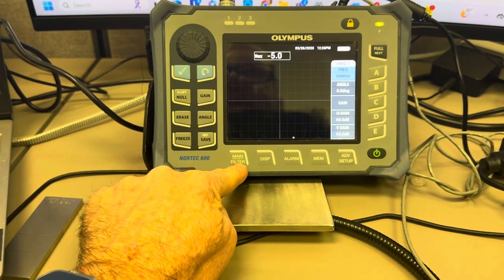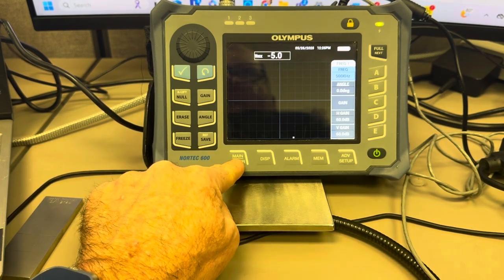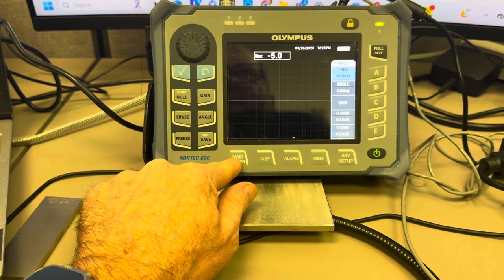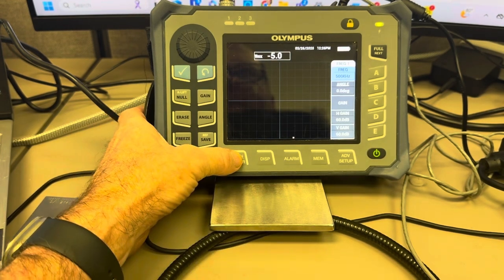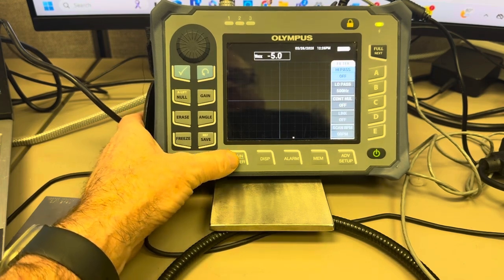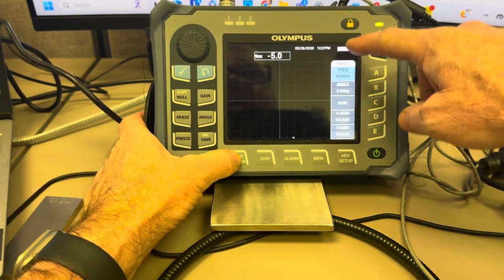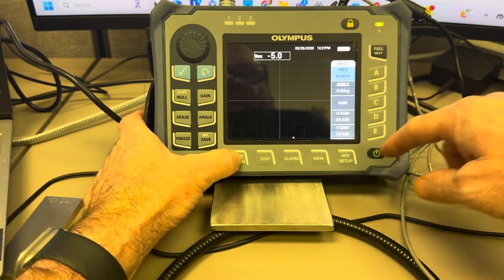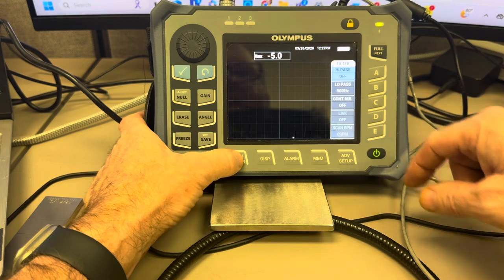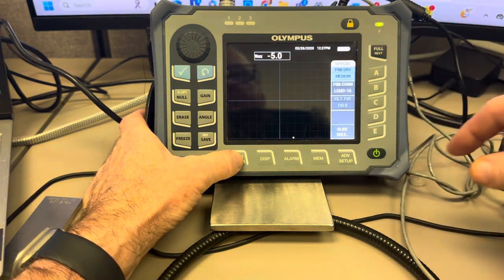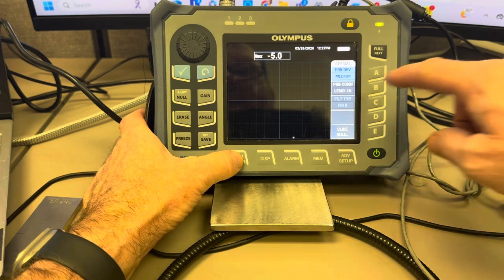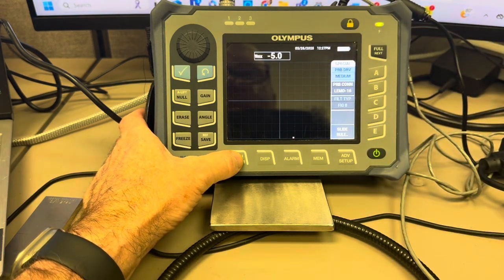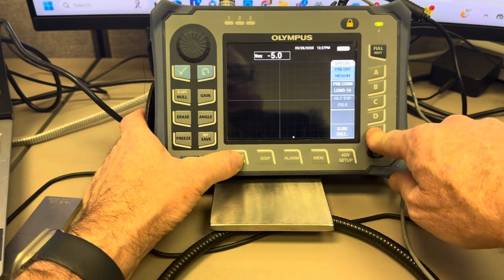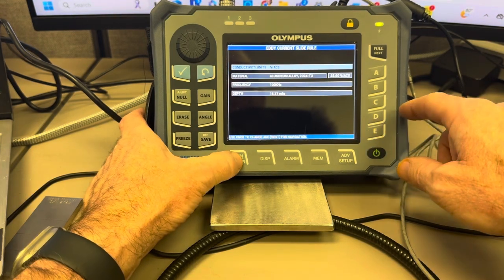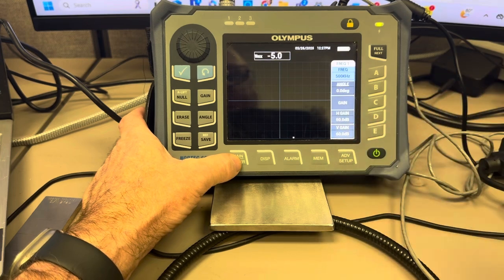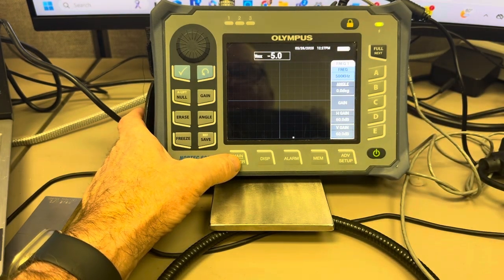Then we've got our main filter button. This provides access to the main menu, which controls other functions such as frequency, gain, angle, and filters. So if I just hit it a couple times, what does it do here? Yeah, so we've got a frequency, angle, gain in horizontal and vertical. If I press it again, it goes into the filter menu. And then if I hit it again, it goes into the special menu like selecting probe drive voltage, the type of cable connector that you have hooked up to the instrument. It's got a slide rule feature in here which helps you determine what frequency you should be using for a test. But right now I'm back into the main submenu, which is the frequency menu.